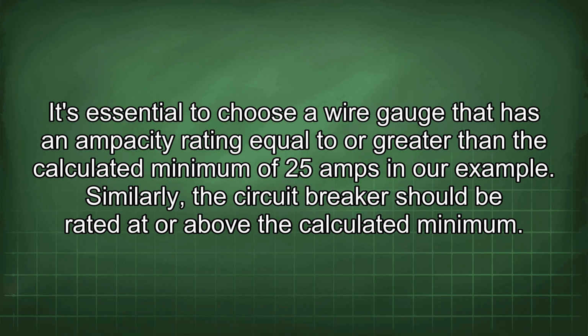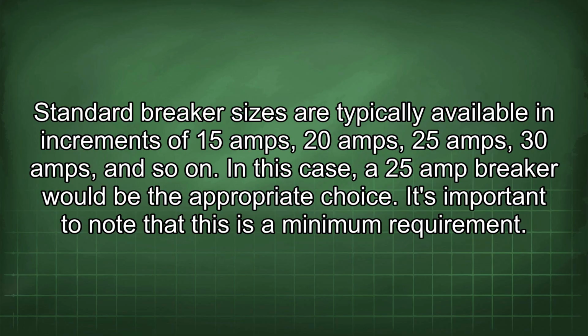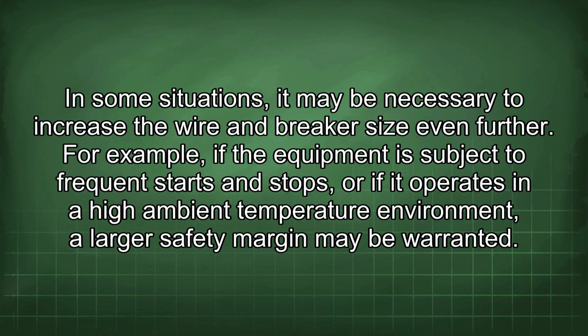Similarly, the circuit breaker should be rated at or above the calculated minimum. Standard breaker sizes are typically available in increments of 15 amps, 20 amps, 25 amps, 30 amps, and so on. In this case, a 25 amp breaker would be the appropriate choice. It's important to note that this is a minimum requirement. In some situations, it may be necessary to increase the wire and breaker size even further. For example, if the equipment is subject to frequent starts and stops, or if it operates in a high ambient temperature environment, a larger safety margin may be warranted.